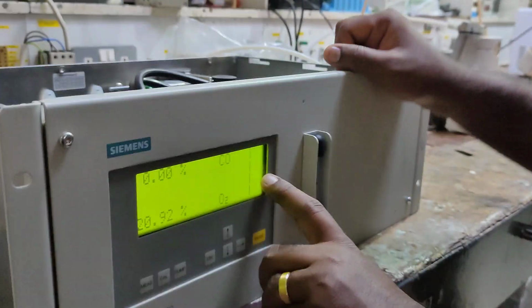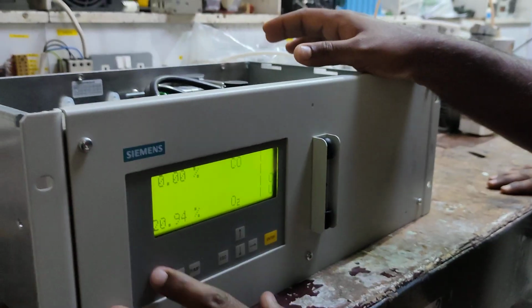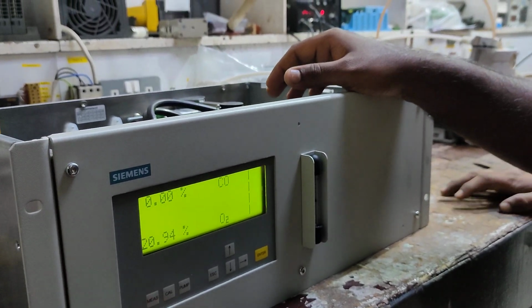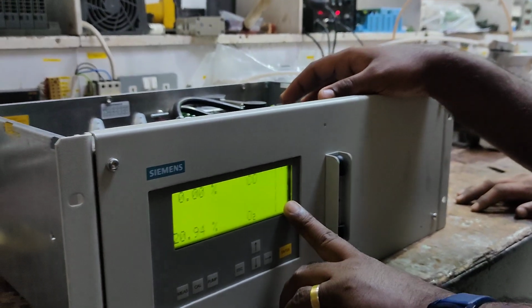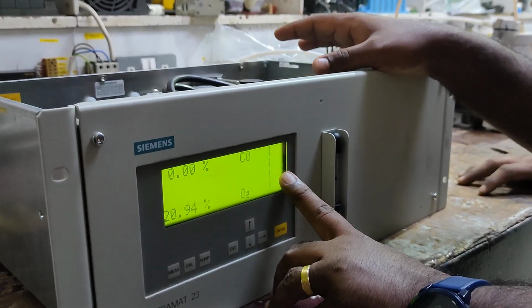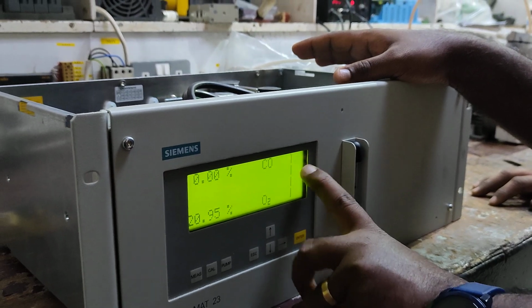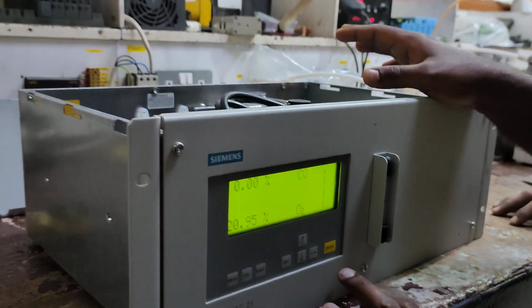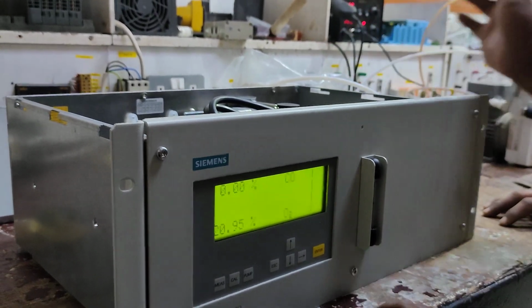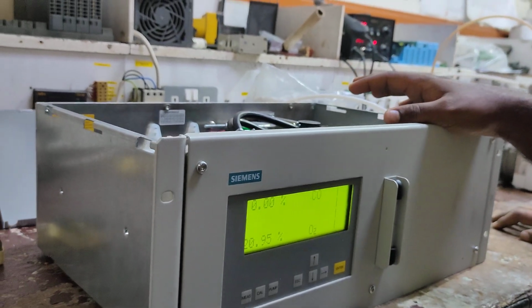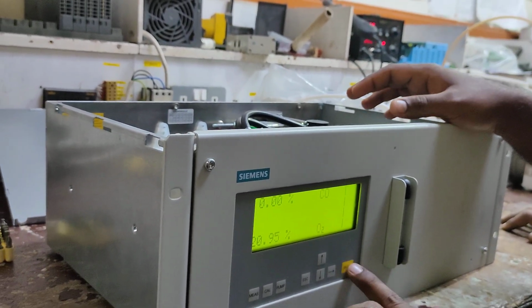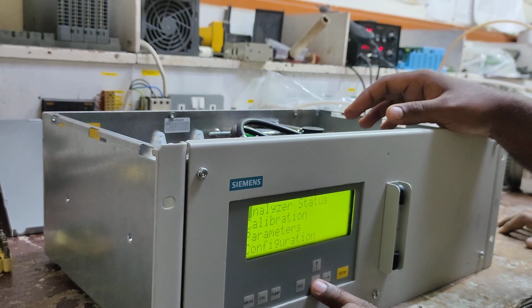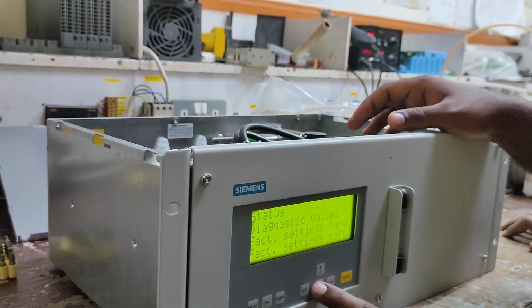Now how do you know that the cell is already heated up? You press measure two times. There should not be any C here. If it is not heated up, it will show C, which means it is in cool mode. If it shows C, then keep the sample out, remove the sample, and let it run with air. How much temperature should it reach, and where can we check?